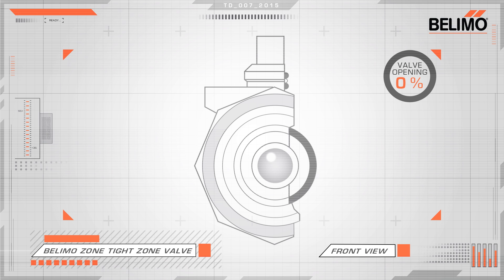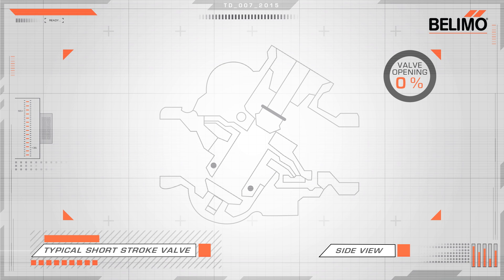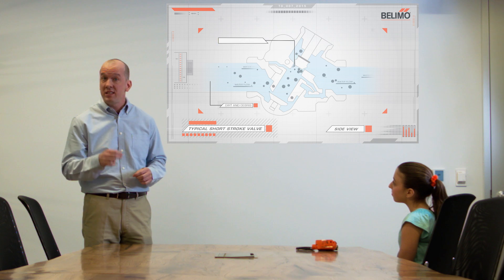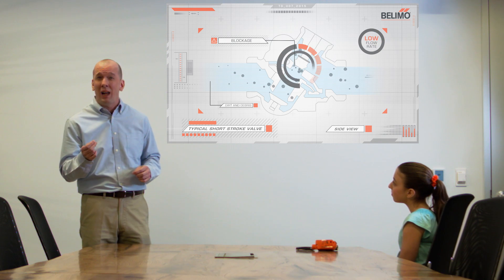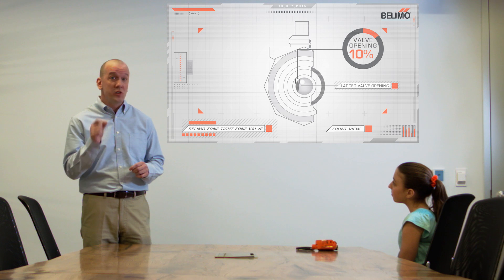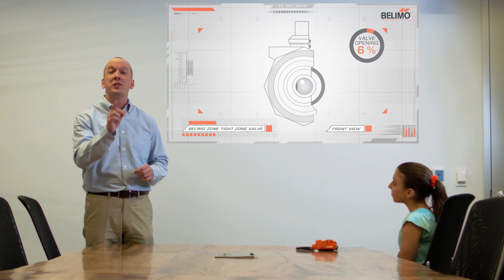This is a special ball — one that has an opening that allows water to pass through. And our opening is much larger than most standard short stroke valves. In fact, most valves operate within a small range, about 10% of the total opening 90% of the time. This tiny opening in typical zone valves can quickly become blocked, preventing the flow of water. The ball valve technology in the Zone Tight Valve ensures that it is never clogged and always closes tight.